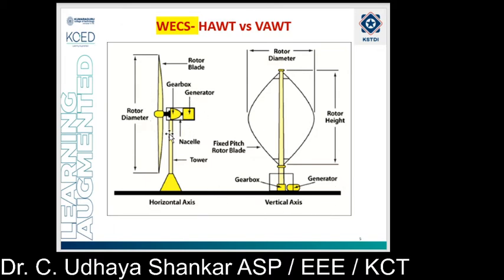In case of HAWT, you can see that the generator and gearbox are maintained at the height of the hub — they are placed in the nacelle on top. Because of this, if there is any failure or maintenance requirement for the gearbox and generator, a maintenance person has to climb to a very high height. This makes maintenance quite difficult compared to vertical axis wind turbine, which is one main cost and accessibility advantage of VAWT.